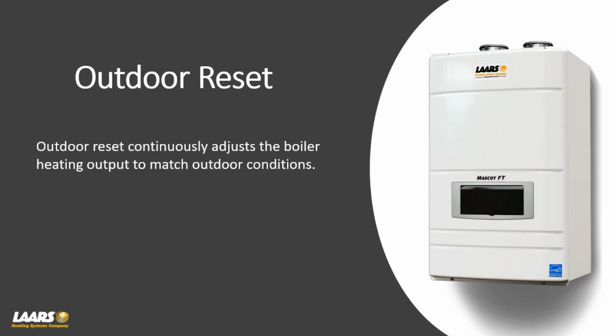Now, Department of Energy mandates residential boilers need to have an outdoor sensor. Example of this, someone's buying a condensing boiler and delivering 180. Are you condensing? No. Especially if you're only designed around a 20 or 30 degree delta T. In my example, if we're supplying 180 and we're designed around a 20 degree delta T, we're returning at 160 and you'll never condense. So outdoor reset allows you, especially during your shoulder months, as it warms up a little bit, you supply less temperature, and now you're returning back potentially at the condensing threshold. So we'll talk a little bit about that.